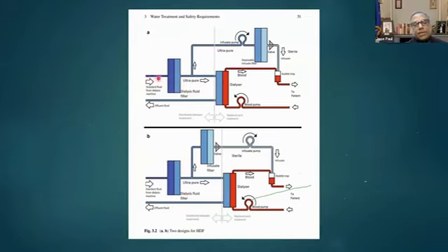The dialysis solution is prepared by the machine from the concentrate and the RO water, and is run through the first filter, which purifies the solution. Ultra pure water goes into the hemodiafilter cartridge, and a part of the ultra pure water goes into the next pump.